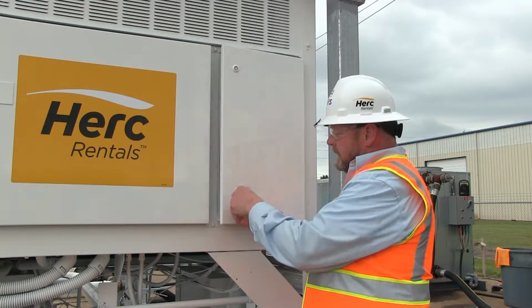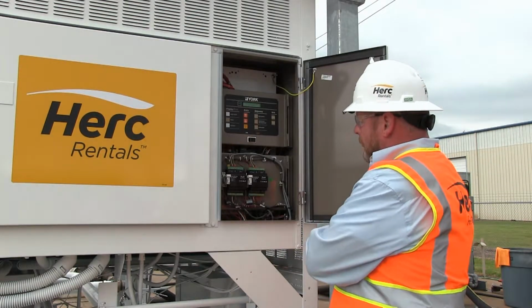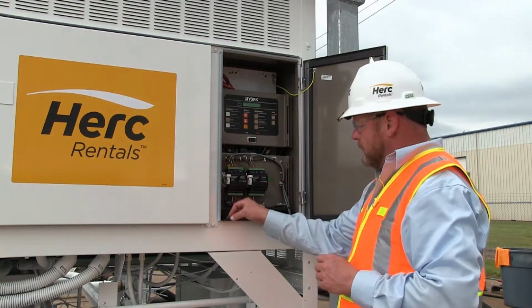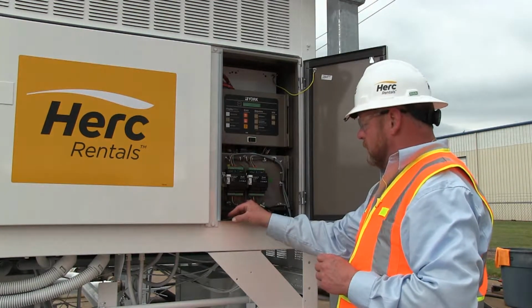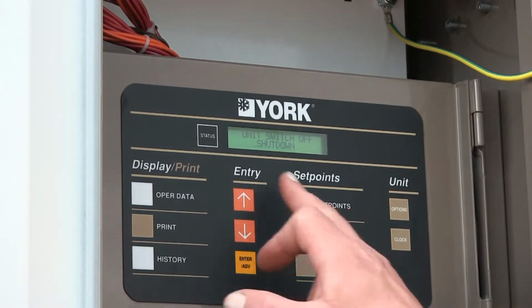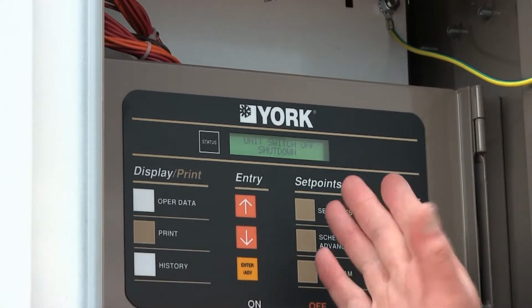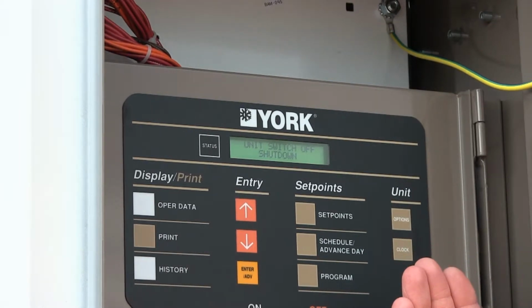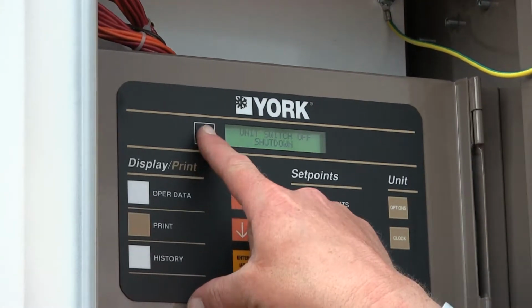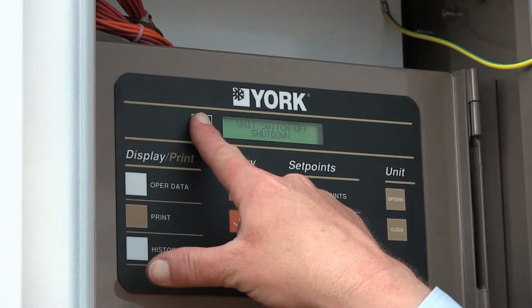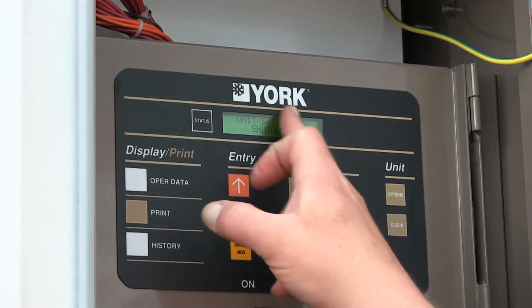So we're just going to open this up. This is a low voltage control panel, and we're going to go through each one of the steps here to get the machine started and get it under full operation. Okay, here's our main display here at the top. This is where it's going to give you feedback, tell you what the machine's doing. The first button I want to go over is the status button. Anytime you push status button, it's like a home button. It tells you what the machine is.